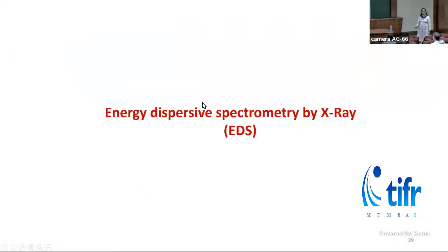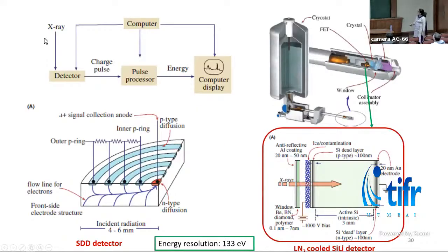Energy dispersive spectrometers are used to find elements present in the sample and also the composition of the sample. When an X-ray photon hits the detector, which can either be a silicon lithium detector or an SDD, that is, silicon drift detector, it creates a charge pulse which is proportional to the energy of the X-ray. This pulse is processed by the pulse processor, digitized and kept in that particular channel. So it has a multi-channel analyzer.